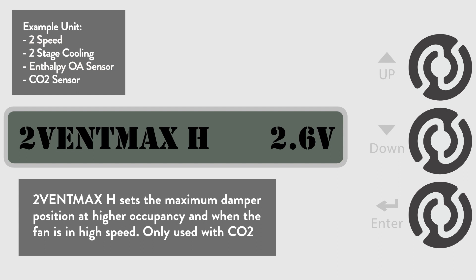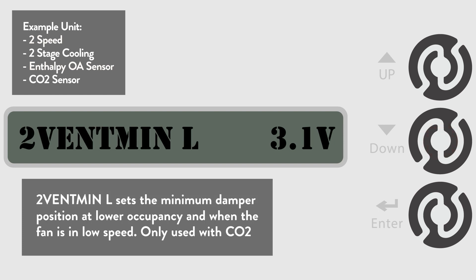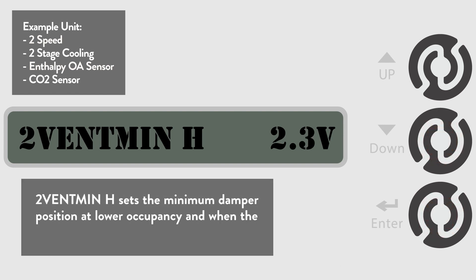Now we will set the minimum outside air position when using a CO2 sensor. This would typically be for spaces with lower occupancy levels. Go to the 2 Vent Min L menu to set the CO2 sensor's minimum non-free cooling position when the unit is in low speed. The default is 3.1 volts, but we are going to change that to 2.9 volts. For the 2-speed unit, set the CO2 sensor's minimum non-free cooling position when the fan is in high speed. The default is 2.3 volts, but we are going to change that to 2.1 volts.